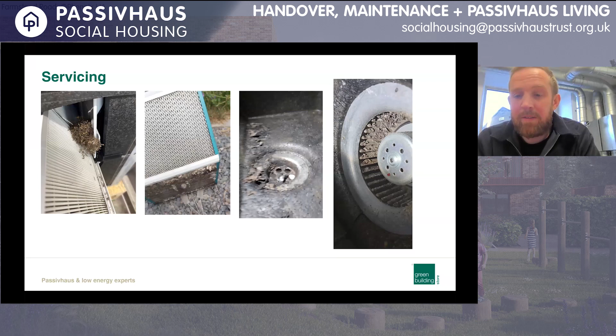And then on the right-hand side, we've got a picture of a fan, which hasn't been cleaned for 10 years. Like I said earlier, you do get some debris making it through the filters. If the filters become very blocked, there's a chance that air could go around the filter. So they need cleaning every 4 years, those fans, and you need to be very careful because they have balancing weights on them. So we tend to use a very fine bottle brush, a lot of patience and a lot of experience to clean them.